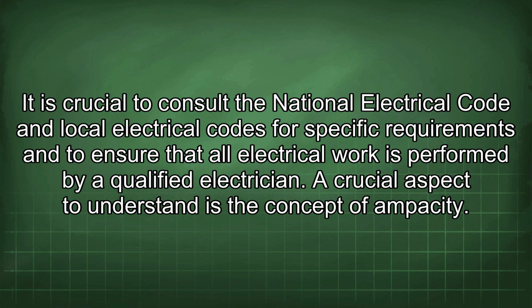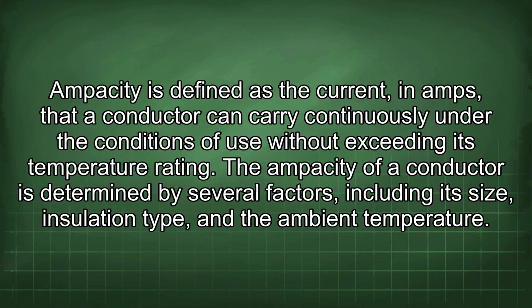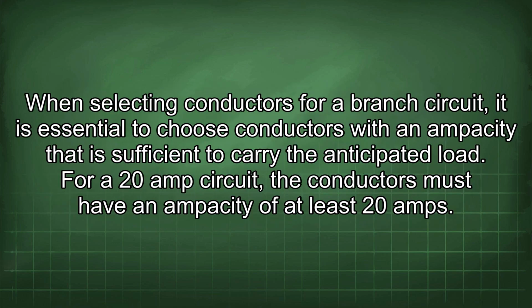A crucial aspect to understand is the concept of ampacity. Ampacity is defined as the current, in amps, that a conductor can carry continuously under the conditions of use without exceeding its temperature rating. The ampacity of a conductor is determined by several factors, including its size, insulation type, and the ambient temperature. When selecting conductors for a branch circuit, it is essential to choose conductors with an ampacity that is sufficient to carry the anticipated load. For a 20 amp circuit, the conductors must have an ampacity of at least 20 amps.